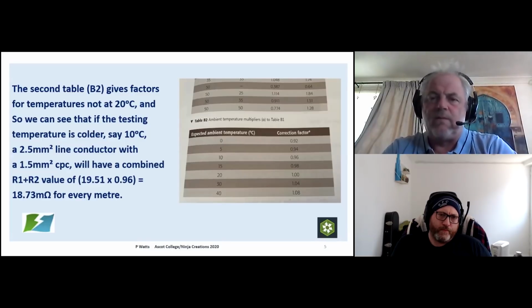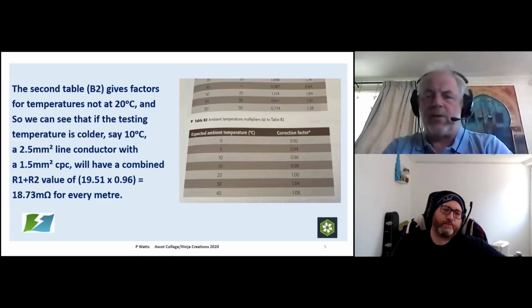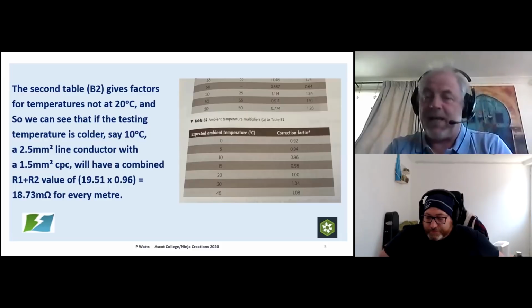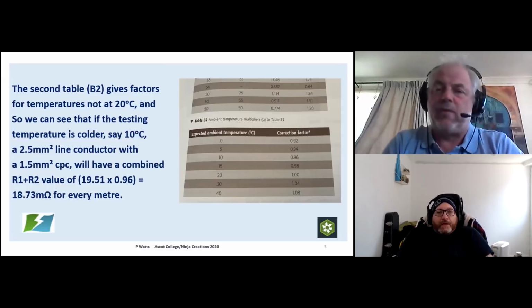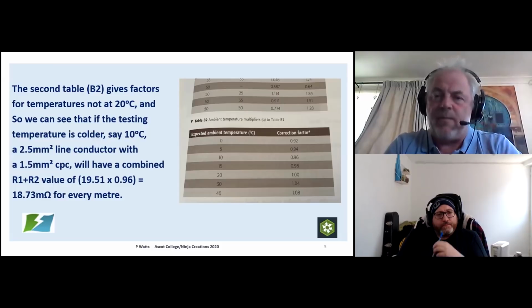They can be sort of 2 degrees. So there's a huge range of temperature there, and our cables are sort of sat in the middle of it. So what factor do we apply? And if we went really silly and went through all the calculations, allowing for that maximum temperature in the middle of summer, we'd end up wiring lighting circuits in 10 mil.